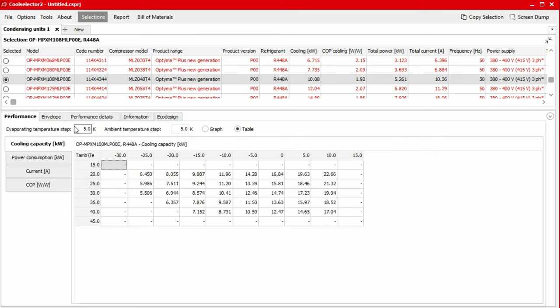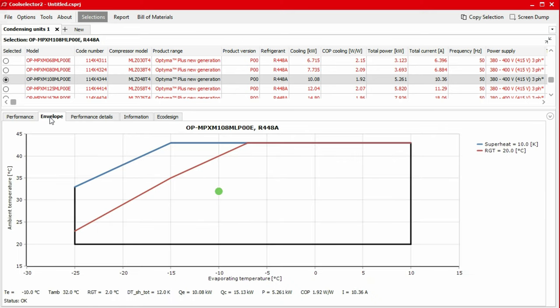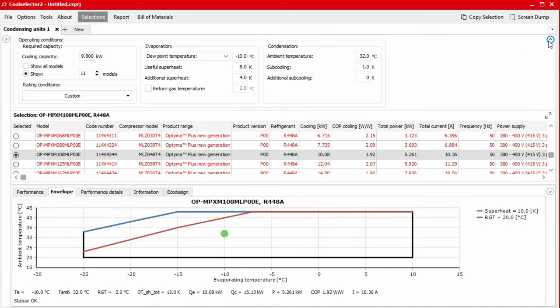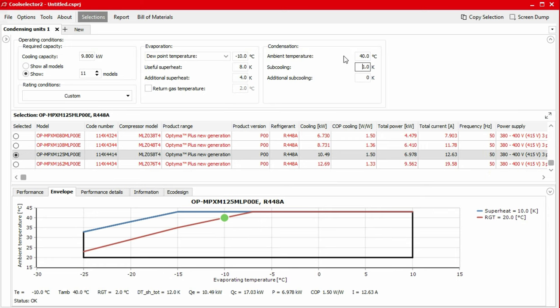Under the envelope tab, we have an interactive graph which represents the limitations of the unit. The green dot represents the compressor's position within the operating envelope according to the operating conditions defined earlier. We can see the green dot will move if we change the values for the temperature for the evaporator or condenser.